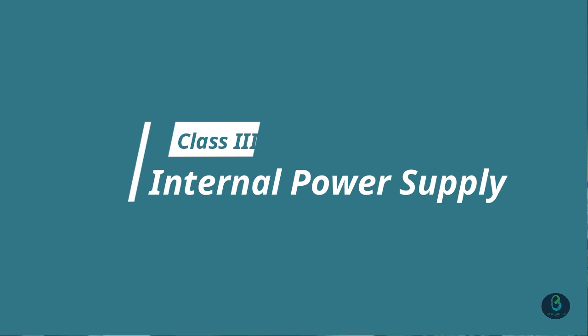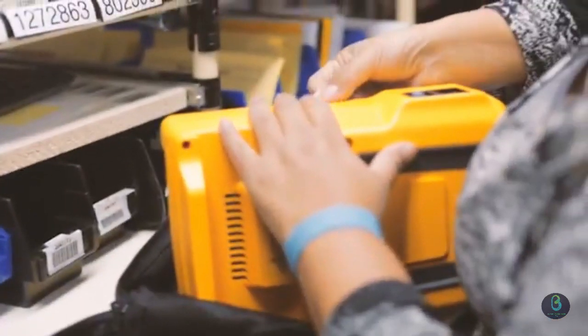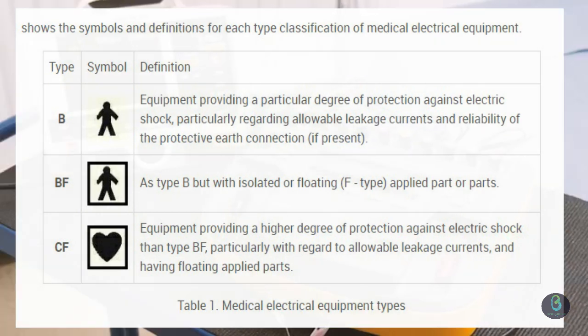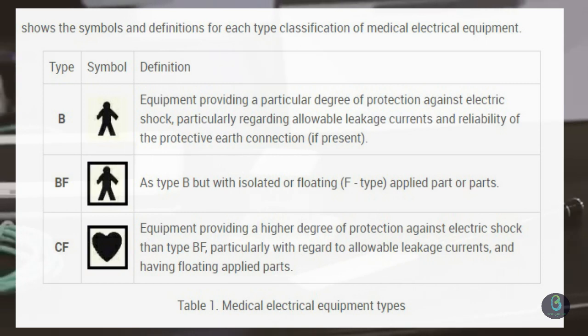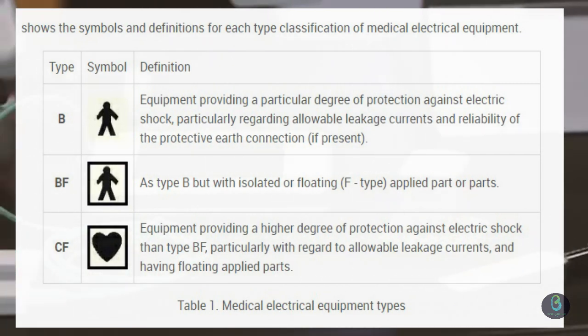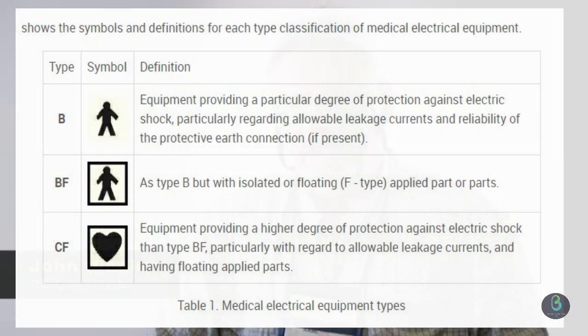Second, each patient applied part or patient lead has a type. Type B: patient applied part earthed. Type BF: patient applied part floating surface conductor. Type CF: patient applied part floating for use in direct contact with the heart.